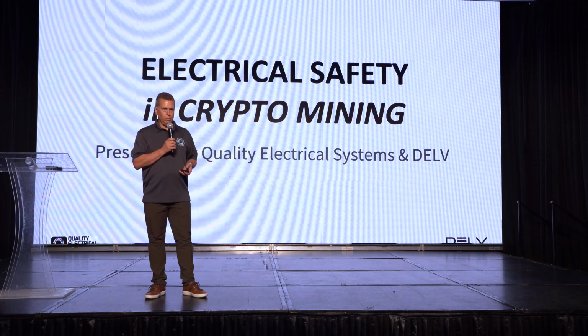Every piece of electrical equipment, if you do an arc flash short circuit study, which is required per the electrical code in almost all installations, should have a sticker on it like this that tells you how close you can get to that piece of equipment safely. It gives you the arc flash boundary and the incident energy, which tells you how much energy is actually available. If the equipment explodes, how much energy does that explosion actually represent? And then it tells you the safe working distance from the equipment.